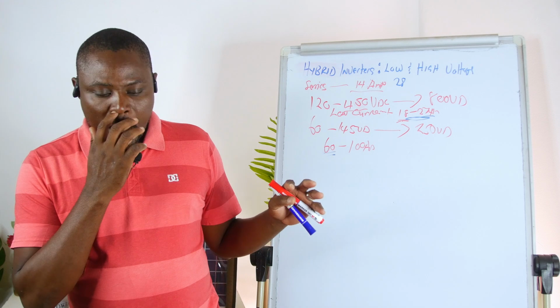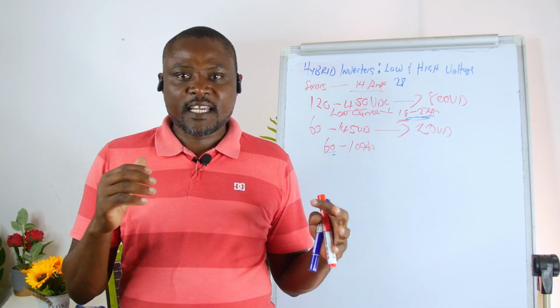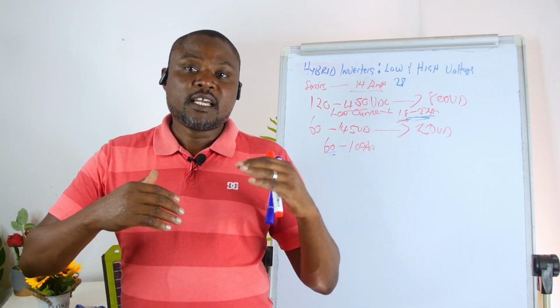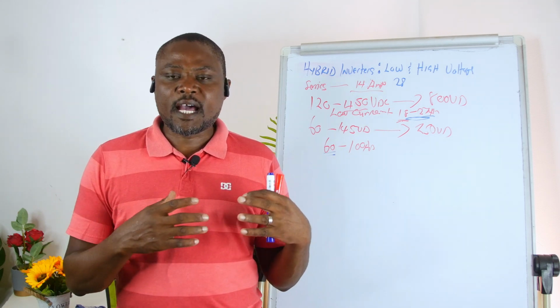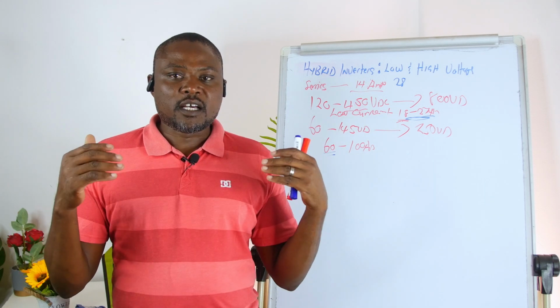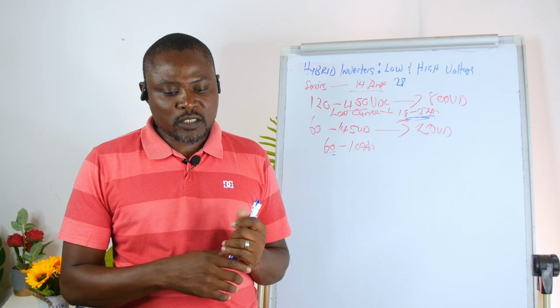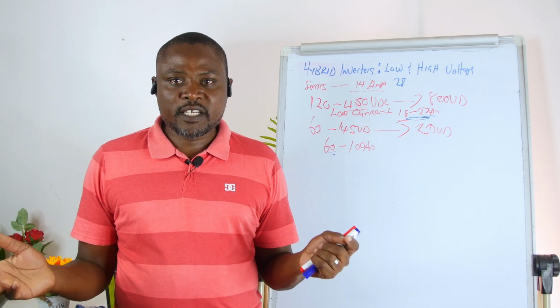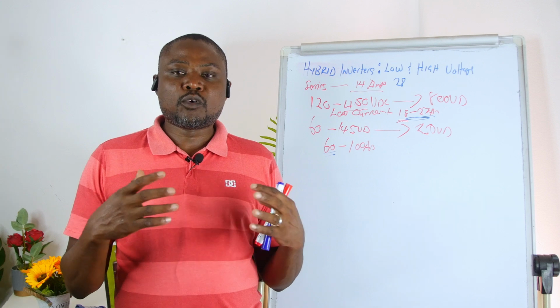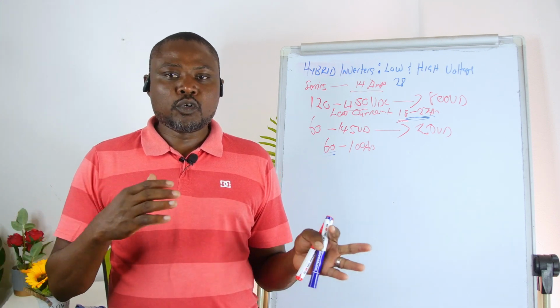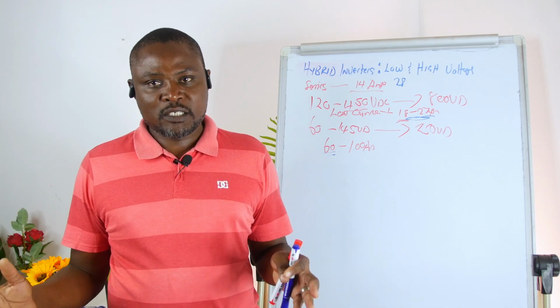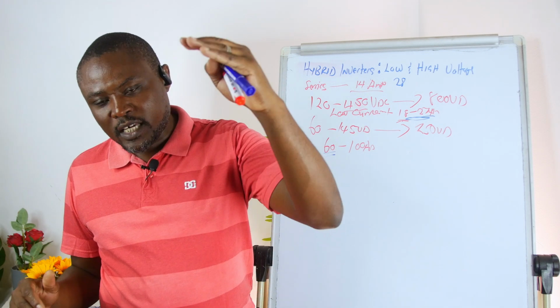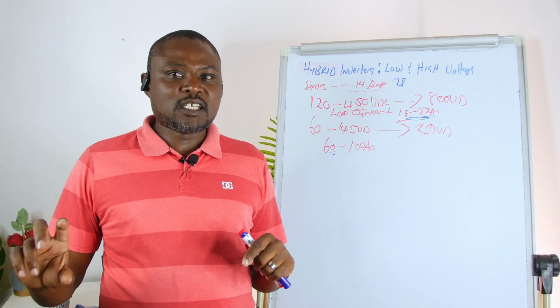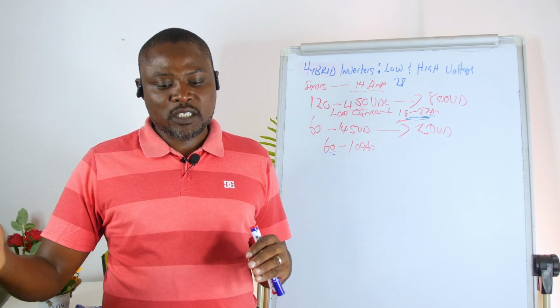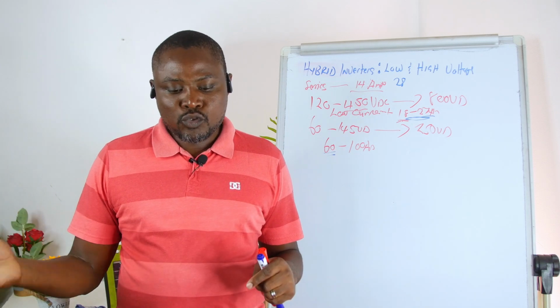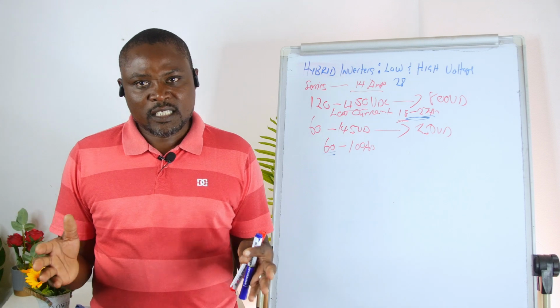We've talked about the MPPT side and how these voltages work. Now let's talk about another aspect that can change on the inverter system, called the high voltage battery configuration. Some batteries come configured for high voltage, and those have to go with a high voltage inverter, which has a high voltage MPPT and a matching high voltage battery configuration. This range can be from 100 to 1000 volts.